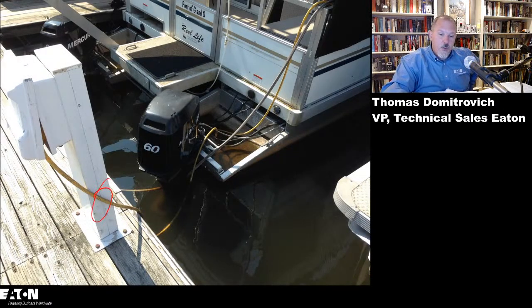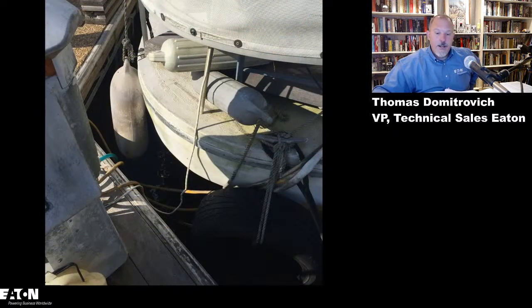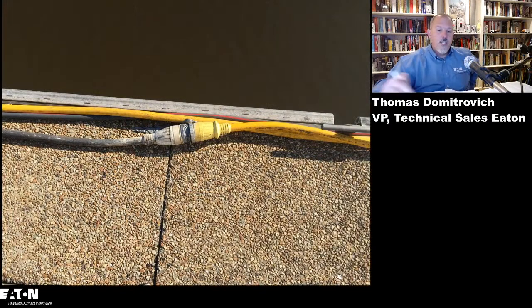You look at this shore power going right down into the water. If this boat comes too close and rubs that conductor, it could energize the water in and around that boat. So this has the ability to float and move in and out, up and down, and rub those conductors and cause a problem. If you just go to some marinas, you will see more and more evidence of this type of wiring - you'll see this type of stuff that goes on.